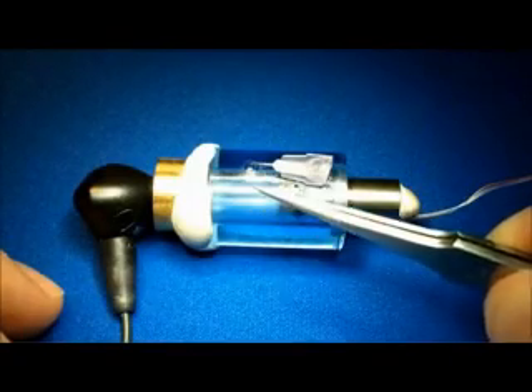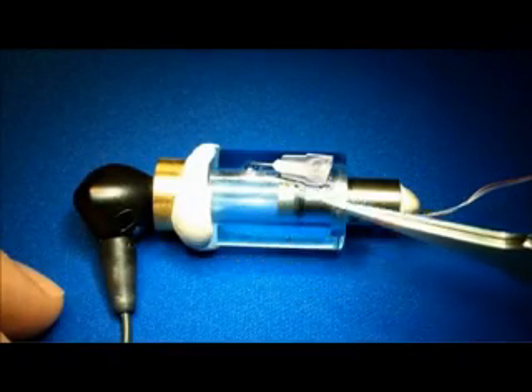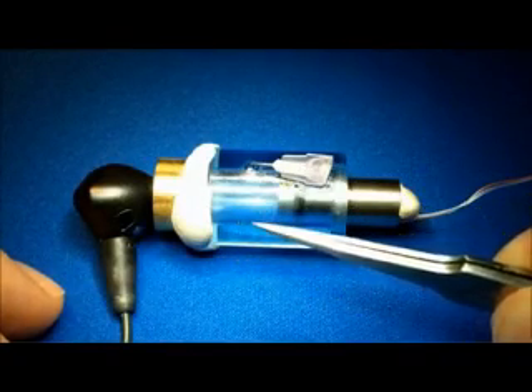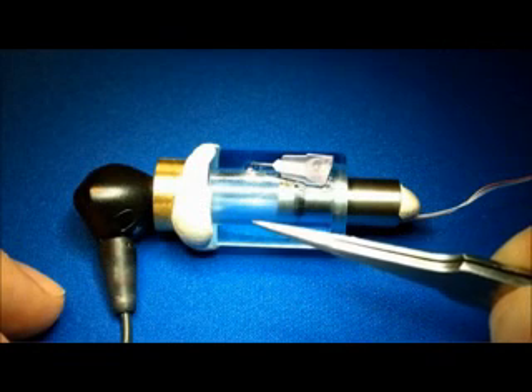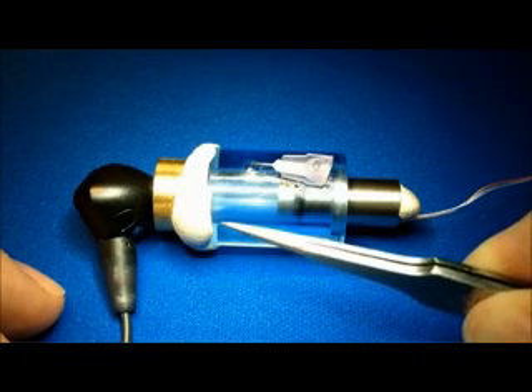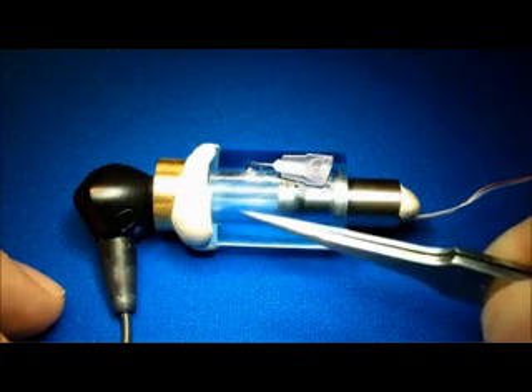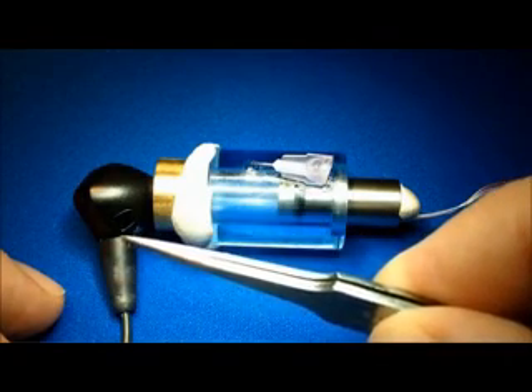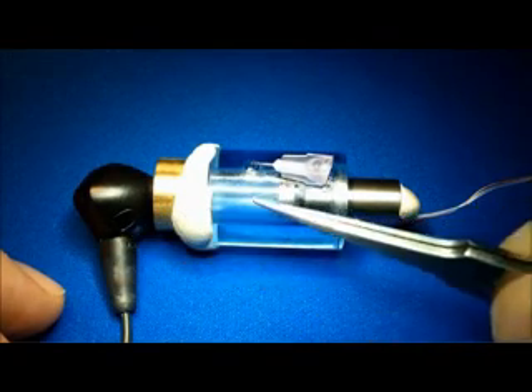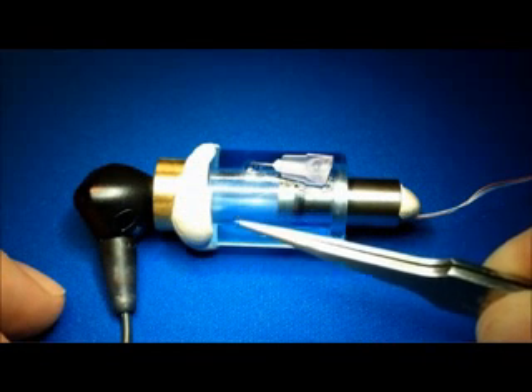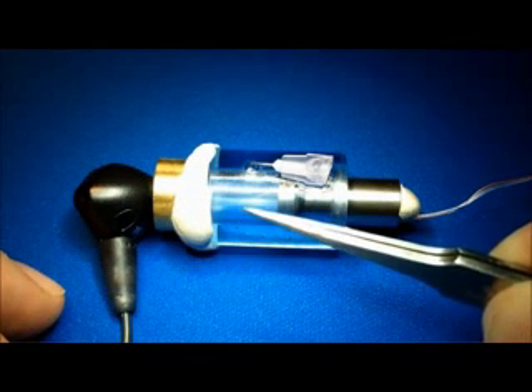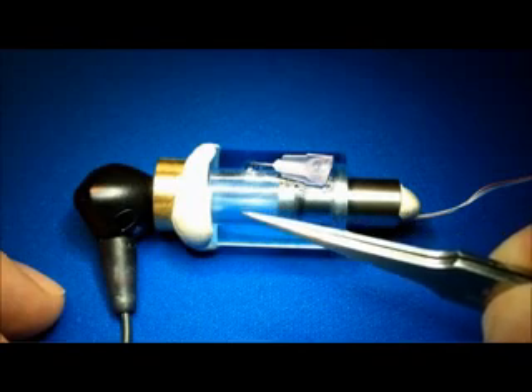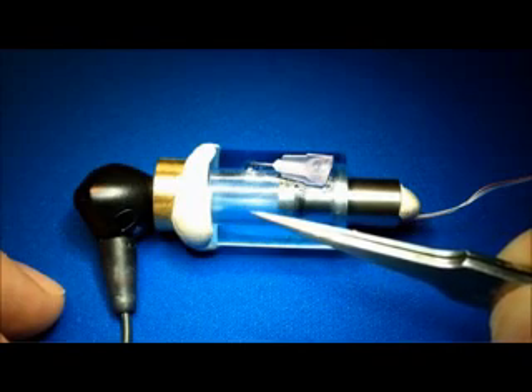Prior to testing, it's advisable to use a volume such as this, which we could call a dead ear, to confirm that our probe signal that's used to test the volume and our excitation signal that's used to excite the Stapedius reflex, that these two signals do not interact with each other. And we'll be looking at that now.